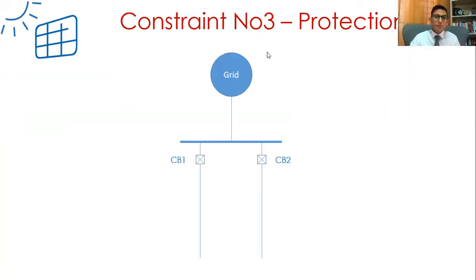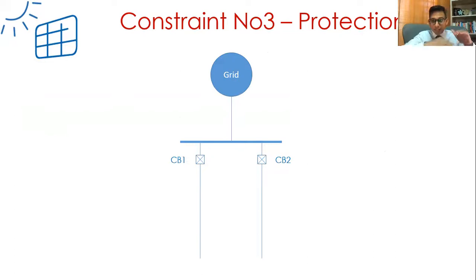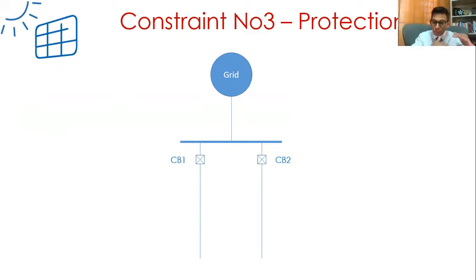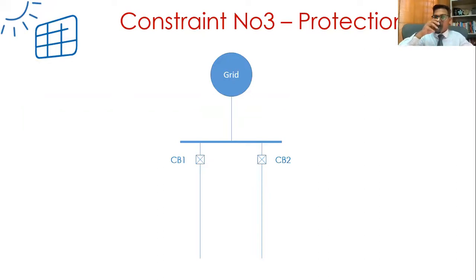We have now seen two criteria: voltage - if left uncontrolled, it can cross regulatory limits - and losses, which decrease to a minimum point then increase again with reverse power flow if DG output exceeds the local load. Now the third one: let's look at protection. We have a grid, two lines, a bus bar, and two circuit breakers - CB1 and CB2. Let's say there's a fault downstream of CB2. There will be fault current flowing from the grid through CB2 to feed the fault. CB2 will trip due to overcurrent protection, isolating that section.